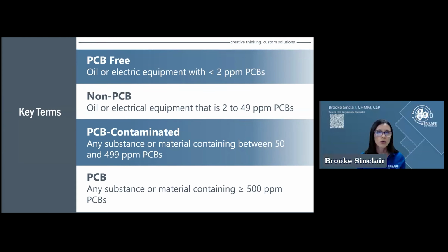Non-PCB is really that 2 to 49 parts per million range, which is technically not regulated by TSCA. But I've taken samples before where one comes back at 45 parts per million and another at 52 parts per million, so be aware that requirements kick in from a TSCA perspective.